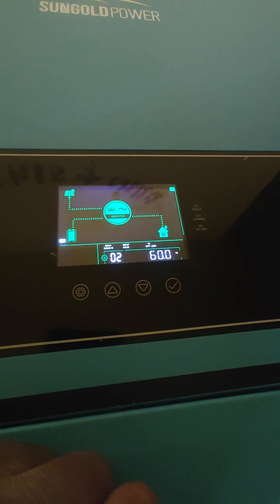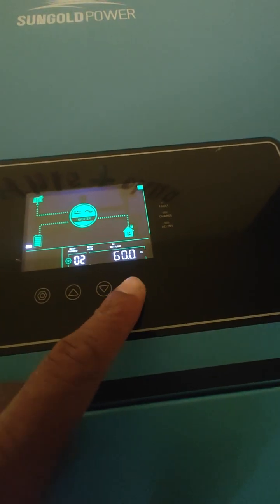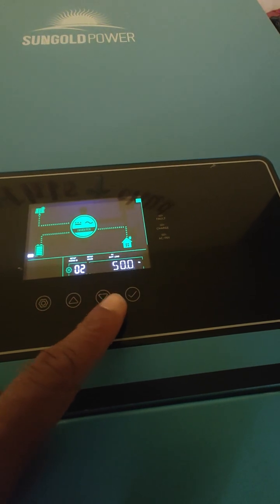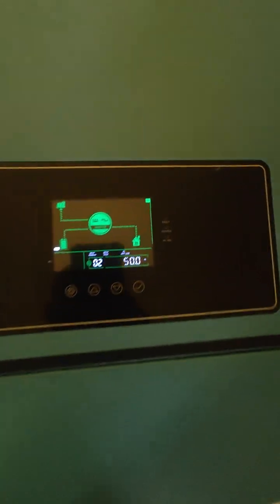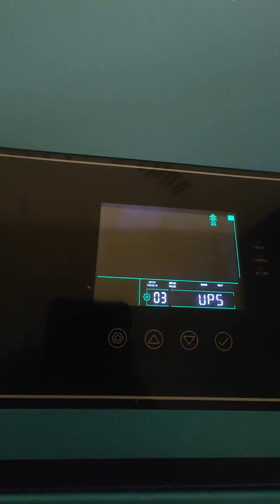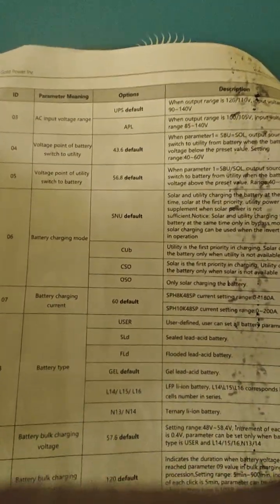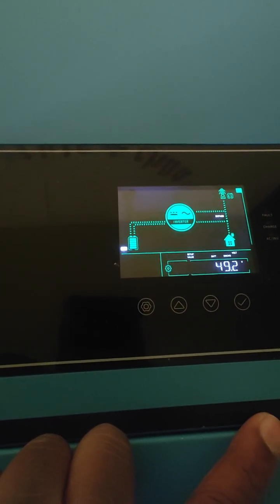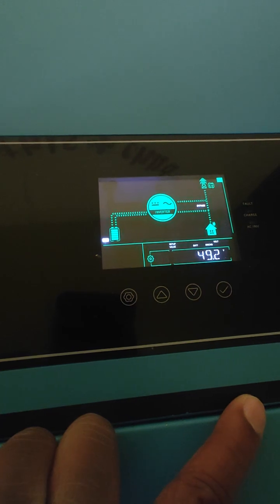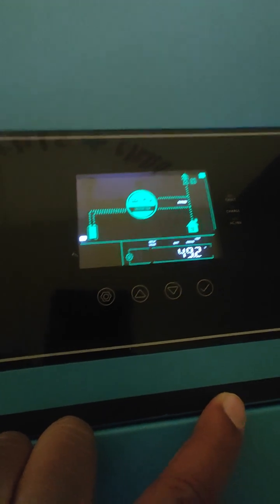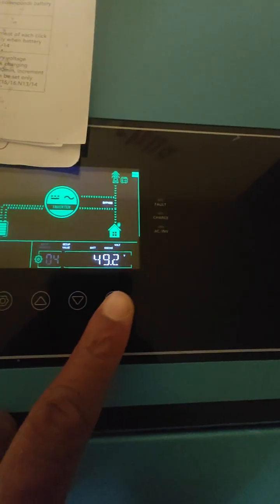Let's go to number 2. Number 2 is the output frequency. Since this is going to Nigeria, I'm going to change this to 50. We'll go to number 3. UPS for the AC input voltage range. And I'm also looking at the parameters here. So I think number 3 is fine as UPS. 4, the voltage point of battery switch to utility. So the default is 43.6, so I'm going to set this back at the default.